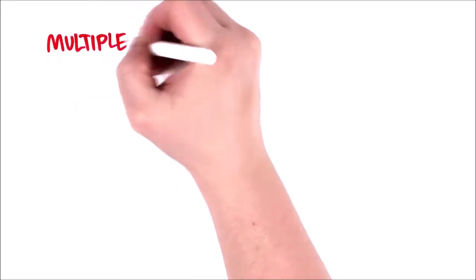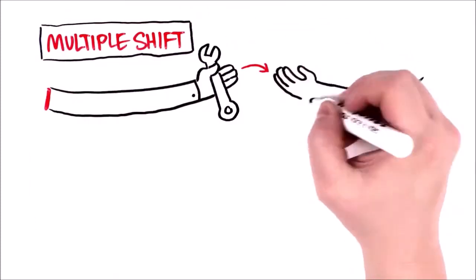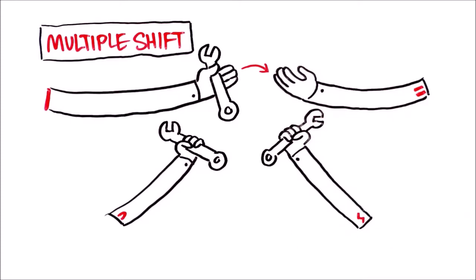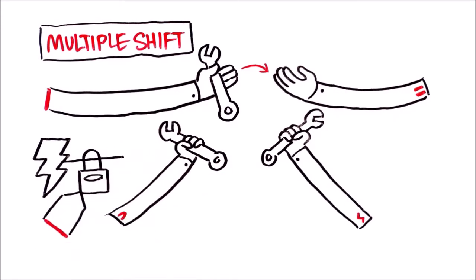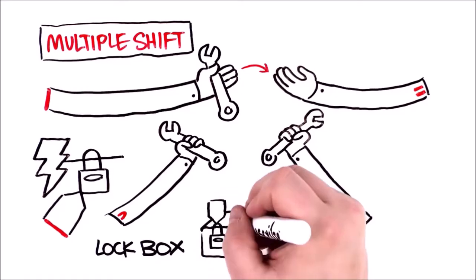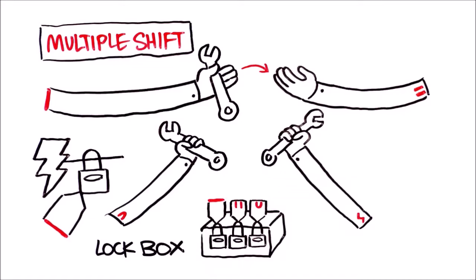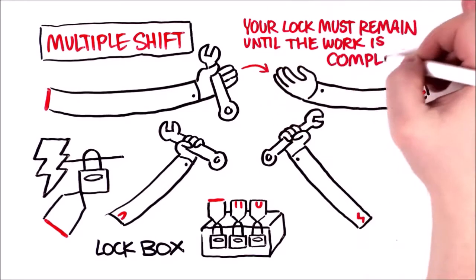What about multiple shift work? Whether it's a situation where you're passing the work onto the next shift or you're performing a group LOTO procedure, it's critical that you maintain continuity of hazardous energy control. Be sure you never leave a lockbox or energy source uncontrolled or unlocked. Usually, one individual is assigned primary responsibility for the lockout. That individual's lock must remain on until the work is complete.